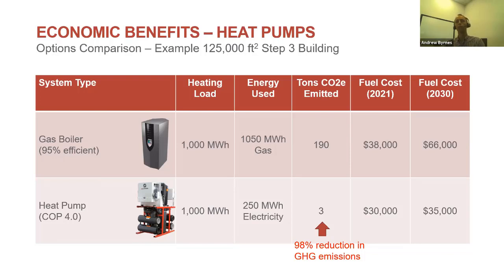Comparing heating with a gas boiler versus a heat pump, let's say both have a 1,000 megawatt hour annual heating load. A gas boiler uses 1,050 megawatt hours of natural gas, whereas a heat pump, operating with a COP of 4 (an efficiency of 400%), would use only 250 megawatt hours of electricity to produce that same 1,000 megawatt hours of heating. So substantially less fuel input with a heat pump, because it's using a small amount of electricity to move heat from an area of cold to an area of hot.